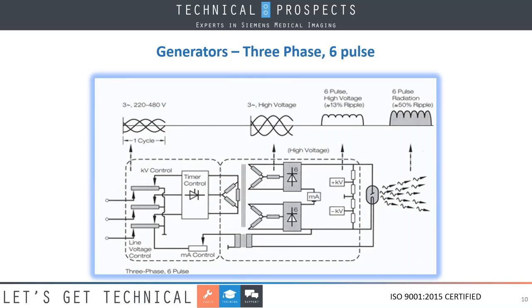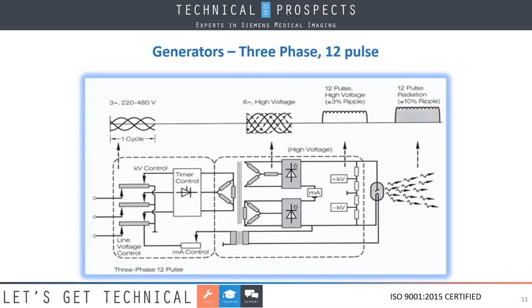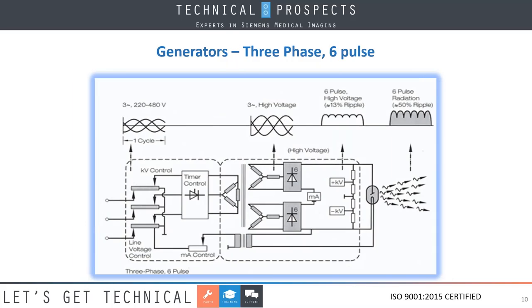Moving on from this one here, if you look at the three-phase circuit, you still see the same basic thing, except now you have three different sides for KV control. You see your timer control in the primary, and then you also see the three-phase six pulse, where you see the delta on the primary and the dual Ys on the secondary. Each one of our transformers has its own rectifier with the MA in the middle, and again, we do the same factor across. However, again, we are still tied here to line frequency.